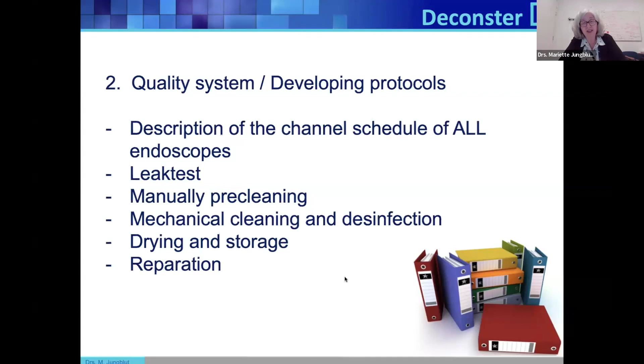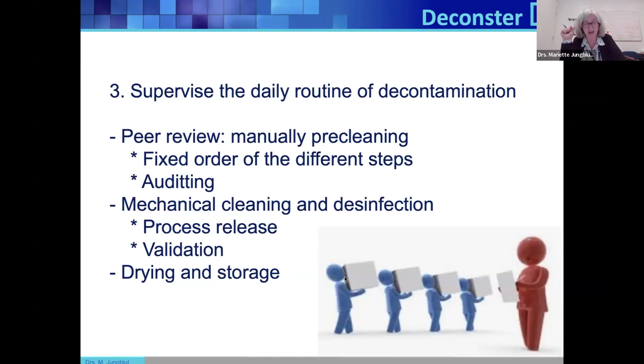Supervising of the daily routine, peer review, as I told you, we have to know the fixed order of the different steps so we can help each other, and auditing at least once a year. Mechanical cleaning and disinfection, process release, whether the machine did the right thing, validation, measuring once a year by knowing the temperature, knowing the concentration, knowing the time, for the mechanical cleaning as well as the drying cabinet, which has to be validated. Next one, please.